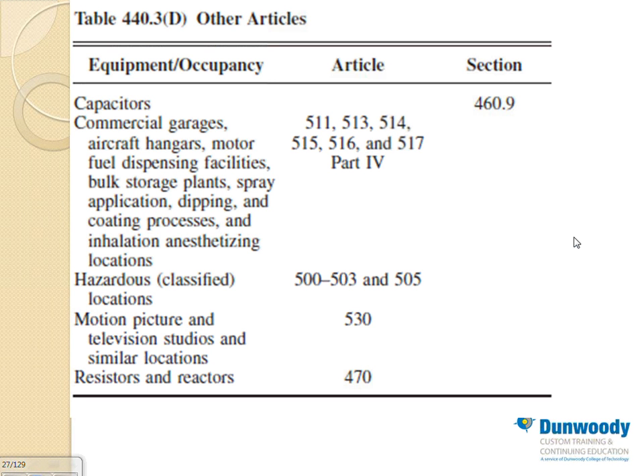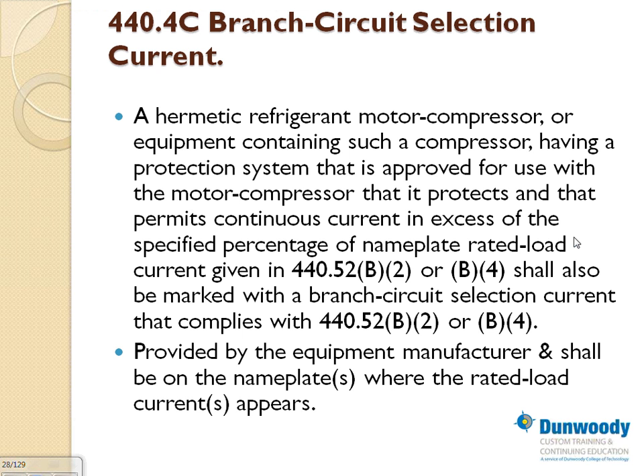A couple of related articles, guys. If, for example, you have a chiller in a hazardous location, what do you think you need to do? You need to consult the hazardous location article for the wiring methods, the wiring equipment, and so forth that you can use in these areas. This just talks about the branch circuit selection current, and you're going to choose the largest of the two. A compressor having a protection system, listed for use with the compressor, permits continuous current in excess of the specified percentage of these values. Anyway, just to summarize, guys, the way I understand it electrically speaking, there are two values. Choose the largest, and size everything based on the largest of the two.